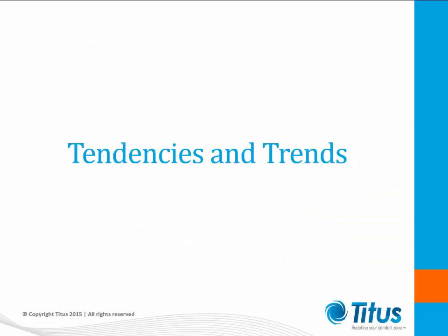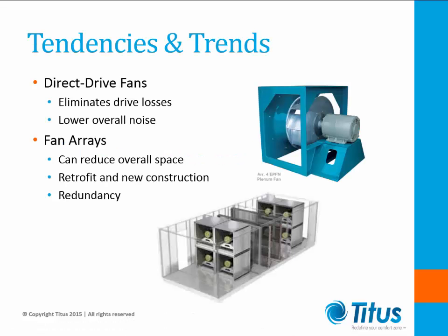Now we're going to take a moment and look at some of the tendencies and trends within the air handling industry. Although much of the technology in air handling units has remained relatively unchanged over decades, some relatively new components and practices are being incorporated that can be useful in the right application. Let's take, for instance, direct drive fans. Direct drive fans eliminate the drive losses associated with belts and can result in higher efficiency and lower overall noise.